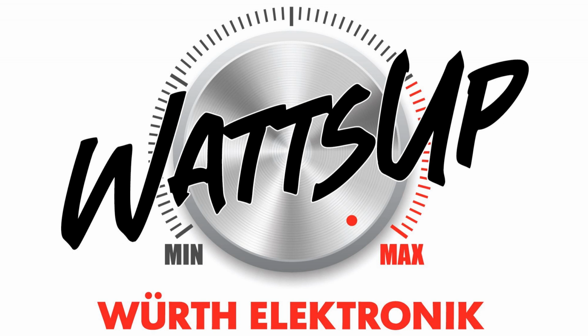So now I go back here in position 1. Now it's difficult to understand, but I'm using another function of the MScope, which is this hide here. I can hide the trace. So for instance, I'm adding the differential mode and the common mode. And now you see why I changed the color: common mode blue, the frozen one, means UT without filter, and common mode red means UT with filter number 1, the big filter.